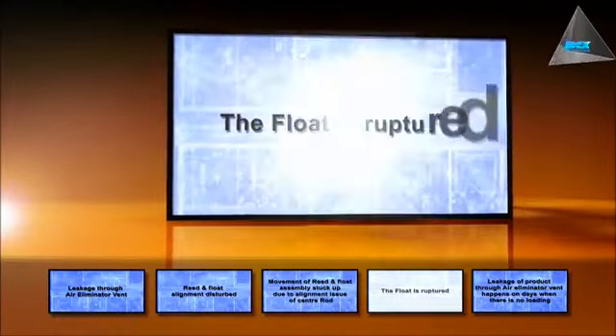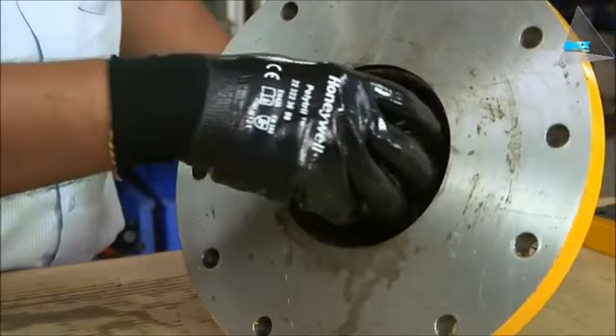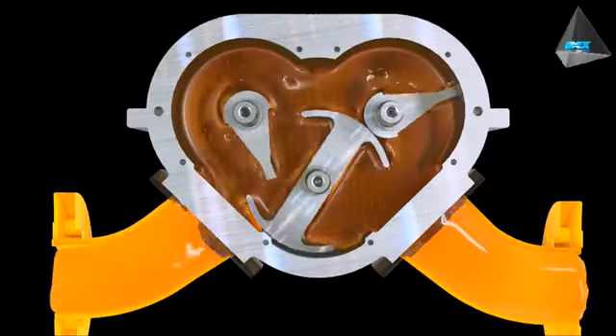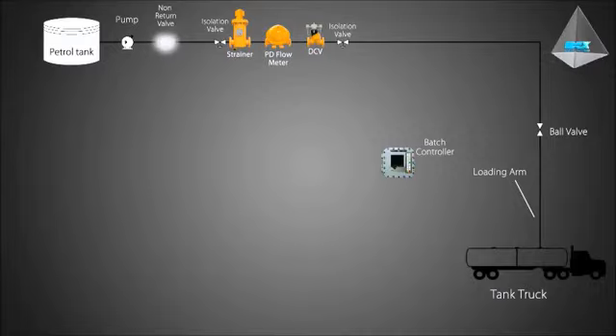The float is ruptured. Solution: replace the float and ensure that the metering system remains full of liquid. Check whether the pump NRV is passing and ensure proper setting.